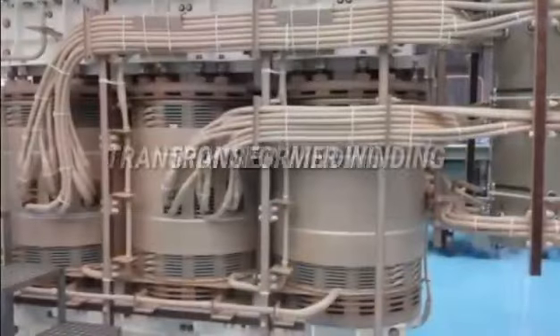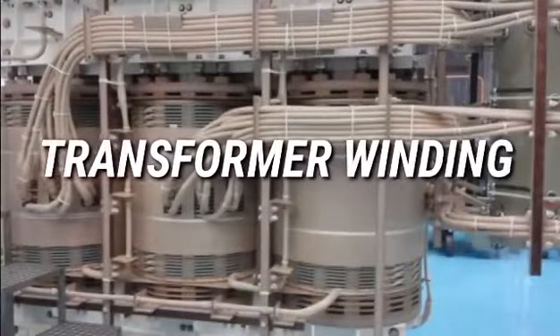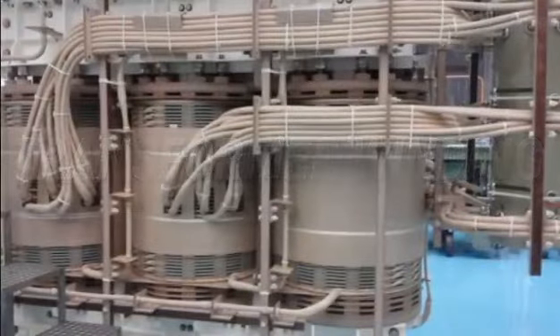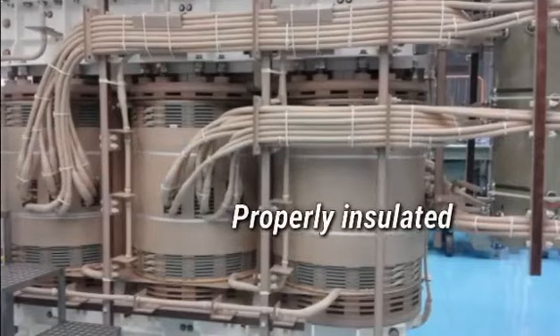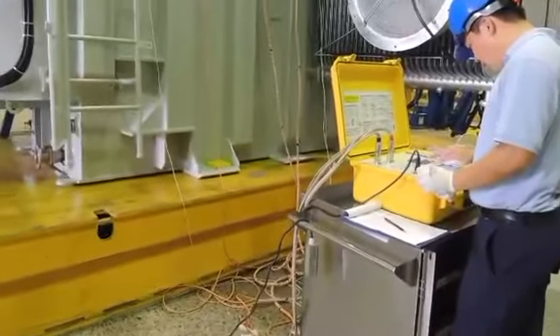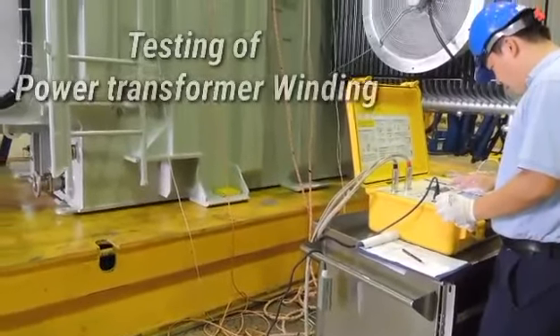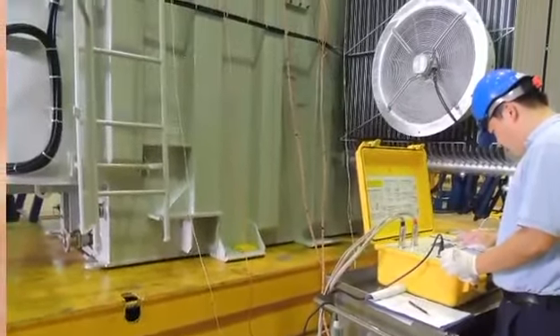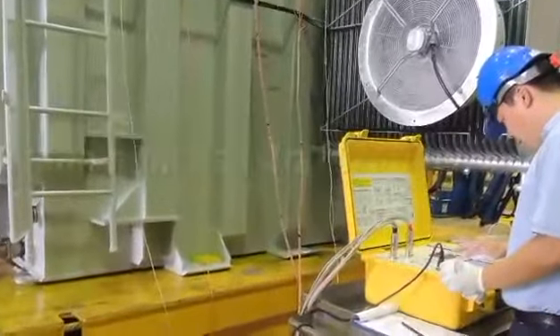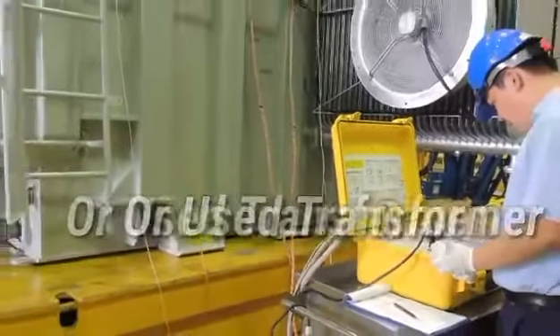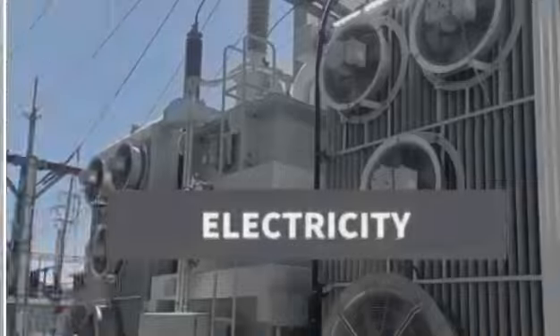The transformer windings consist of the current-carrying conductors wound around the sections of the core, and these must be properly insulated, supported and cooled to withstand operational and test conditions. This video will show you the way to test the winding of the power transformer, if it is a brand new transformer or it is going to be put into service. If you are ready, let's get started.